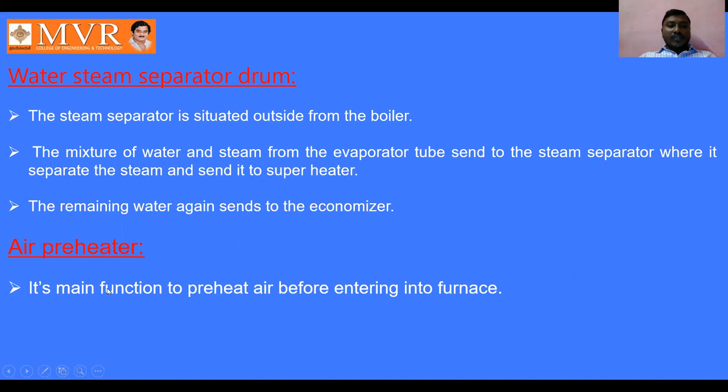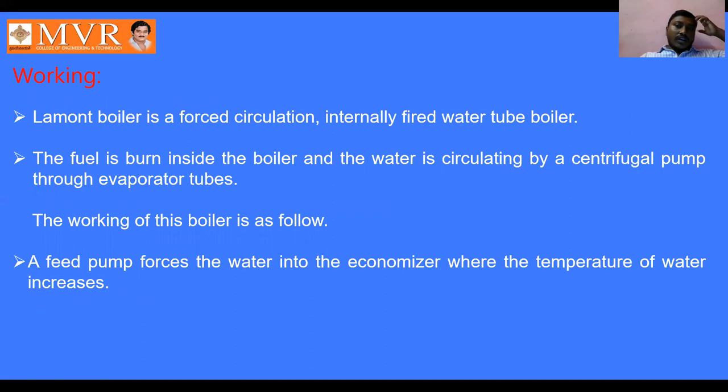And air preheater, which preheats the air before entering into the furnaces. What I have explained to you about the working principle of the Lamont boiler near the diagram, we are going to get in a step-by-step manner here. The Lamont boiler is a forced circulation boiler. Forced, why? Because we are using pumps for pumping the air or feed water into the boiler.